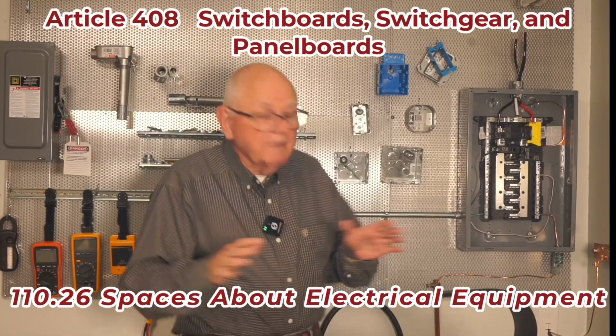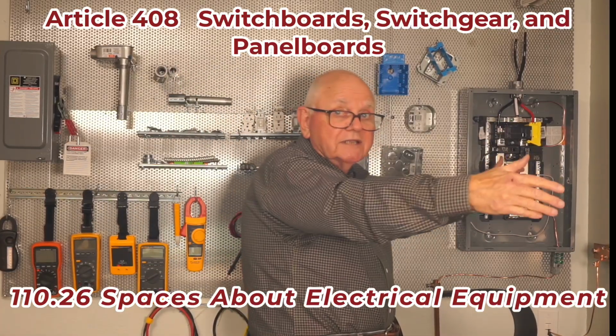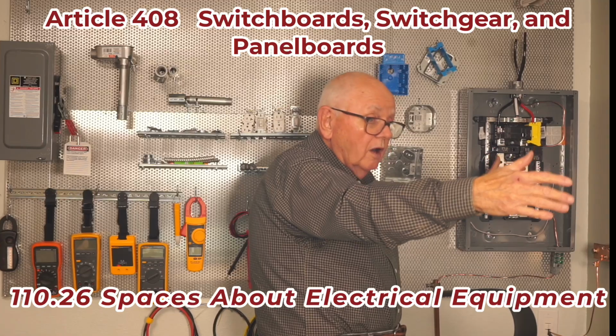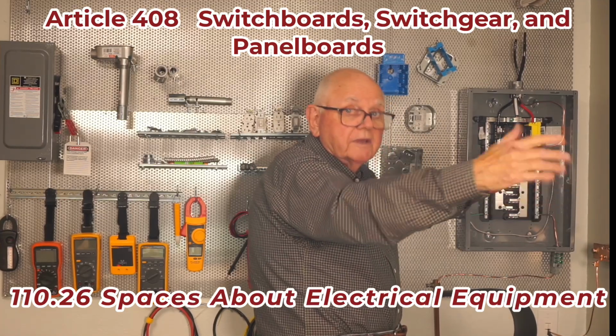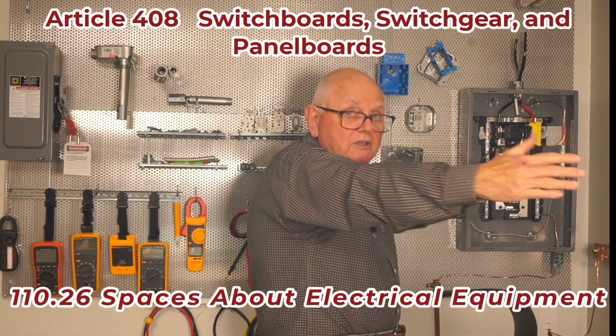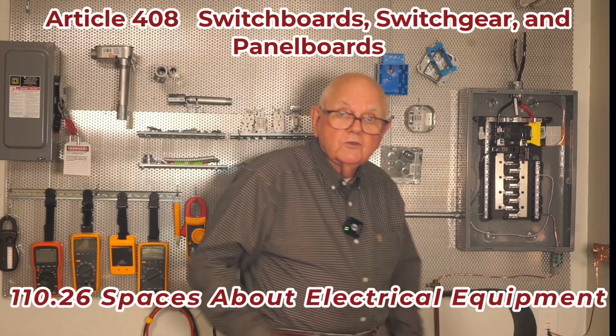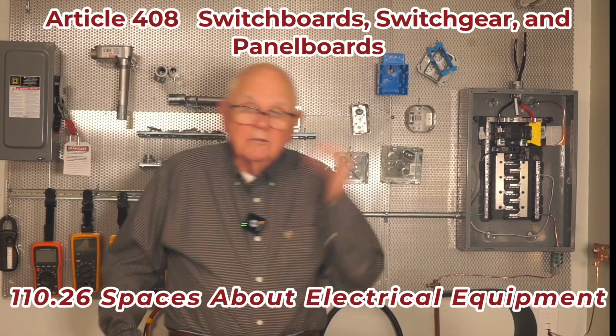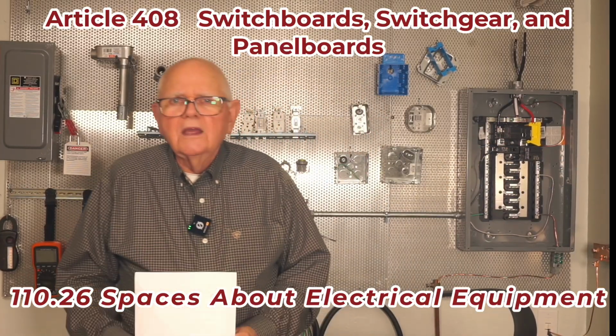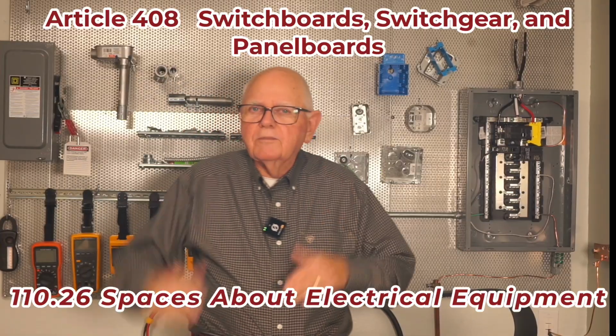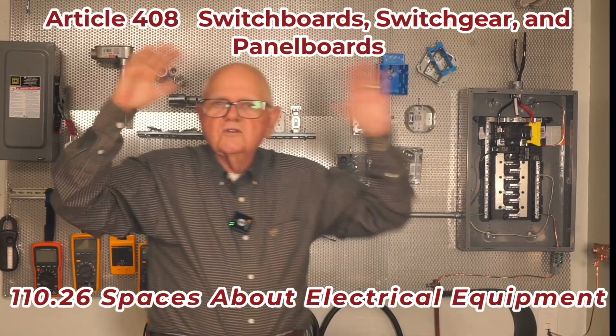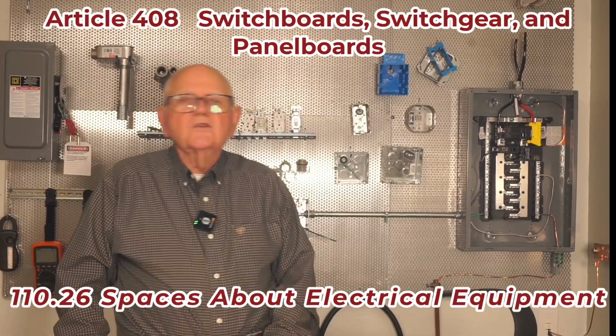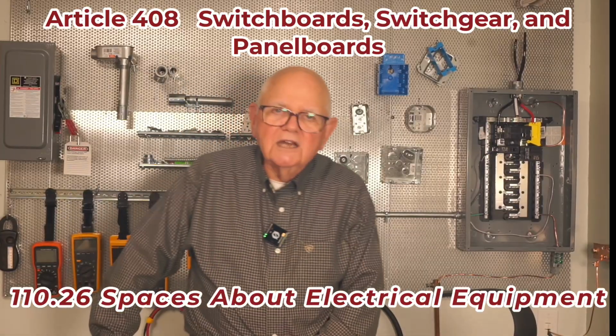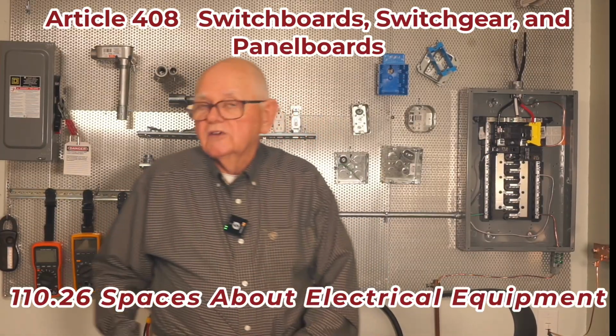There are tables based on whether I have an uninsulated wall, an insulated wall, or another piece of electrical equipment with a certain voltage, how much room I have to have between those two pieces of equipment or between that panel board and that wall and so on. Spaces about my electrical equipment, height requirements, no water dripping down, drip pans, all of those requirements I find in 110.26, as well as your storage requirements.